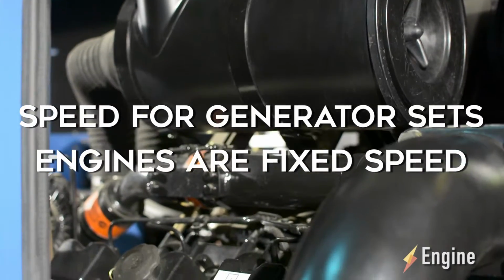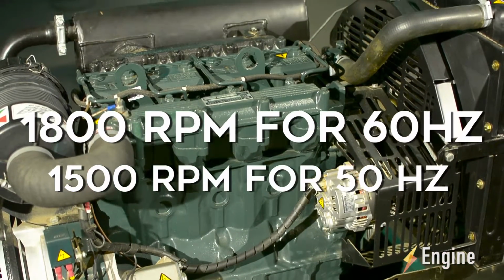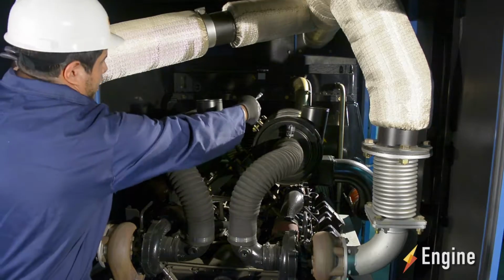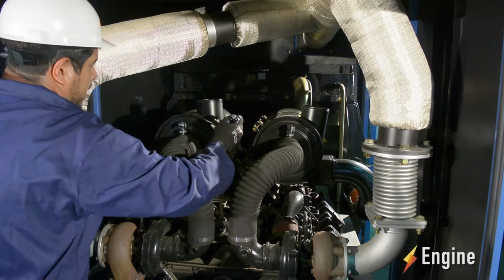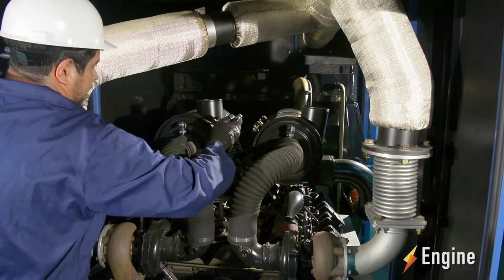The speed for generator set engines are fixed speed, usually 1800 RPM for 60 Hz and 1500 RPM for 50 Hz. There are also medium and low speed engines that are typically used for prime power applications.